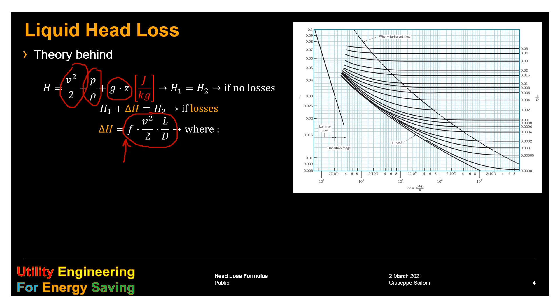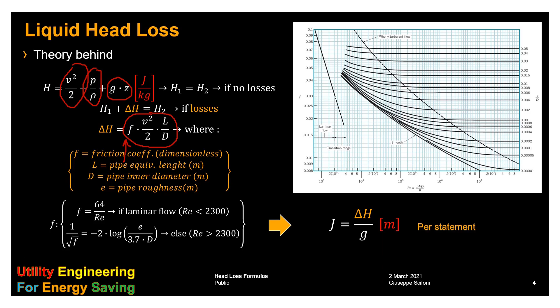In this presentation, we take care of head losses due to the friction in the pipe, proportional to the square of the speed, to the length of the pipe and inverse to the diameter, as per the formula displayed. The friction coefficient F is given by the Moody chart, the chart on the right side, and it can be also calculated by the formula in the brackets: for the laminar, 64 divided by Reynolds number, and for the turbulent, when Reynolds is greater than 2300, we have this more complex formula, not dependent upon Reynolds, but only upon the roughness E and the diameter D. And the practical expression of the head loss is in meter, so it is, as per statement, delta H divided by the gravity constant G.